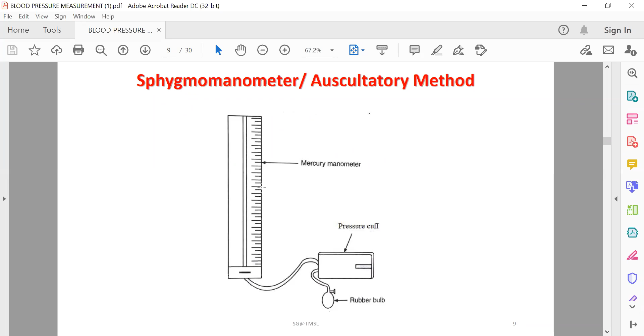Actually, the principle of the sphygmomanometer is that when the cuff is placed over the upper arm and inflated, arterial blood can flow past the cuff only when the arterial pressure exceeds the pressure in the cuff.